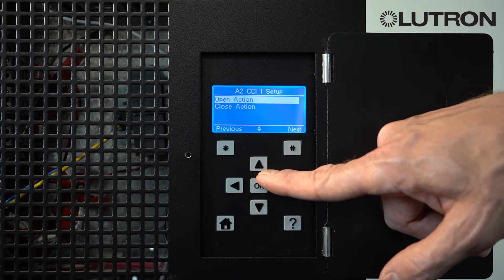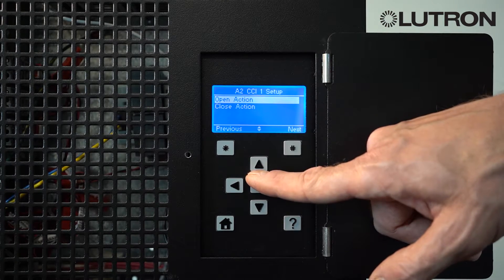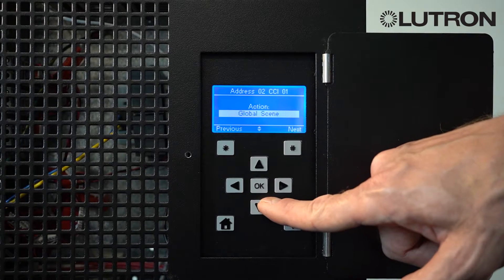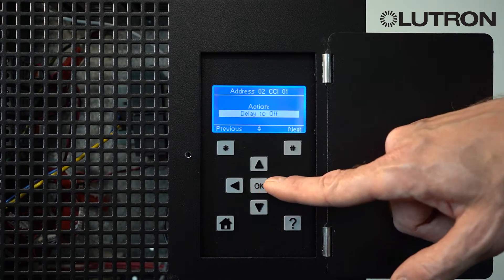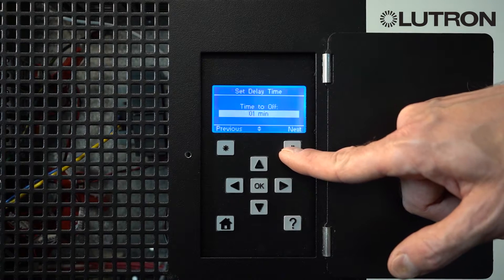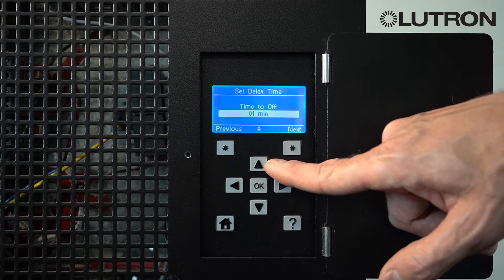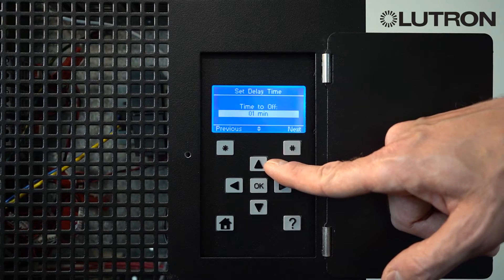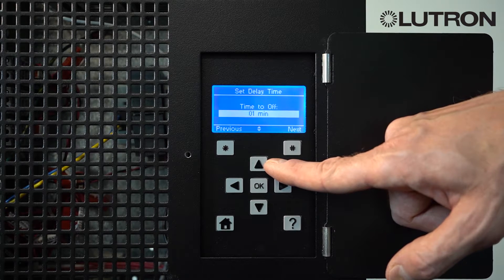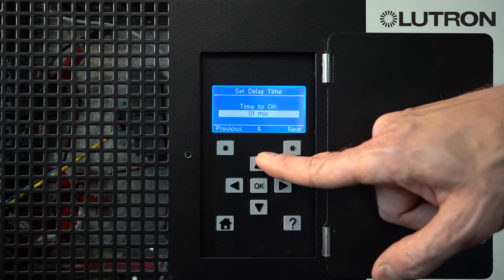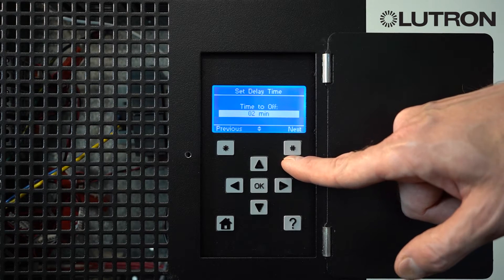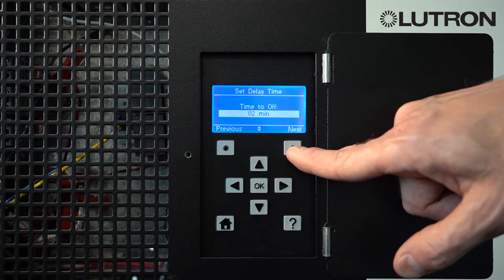To select what happens when the room goes unoccupied, select Open Action, then choose Delay to Off if that setting is not already chosen. When you click Next, it tells you how much time it will take for the lights to turn off after the room becomes unoccupied. This is in addition to any time set on the sensor itself. So if your sensor time is at 8 minutes and you set this time-to-off for 2 minutes, the room will have to be unoccupied for a total of 10 minutes before the lights turn off.